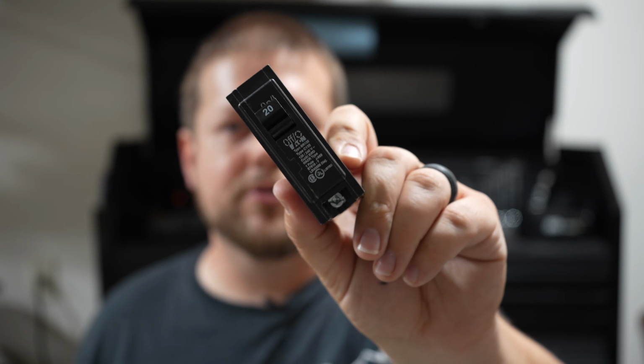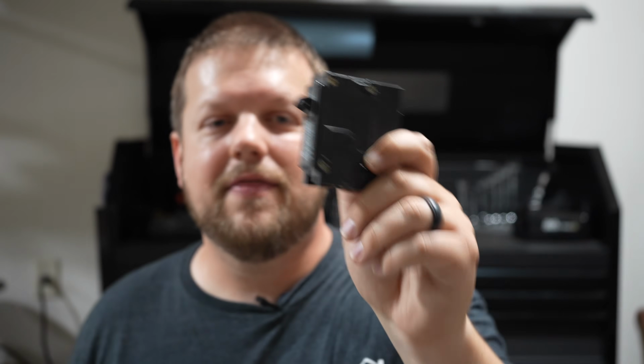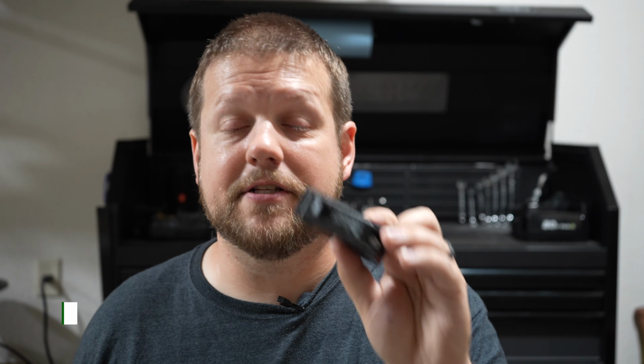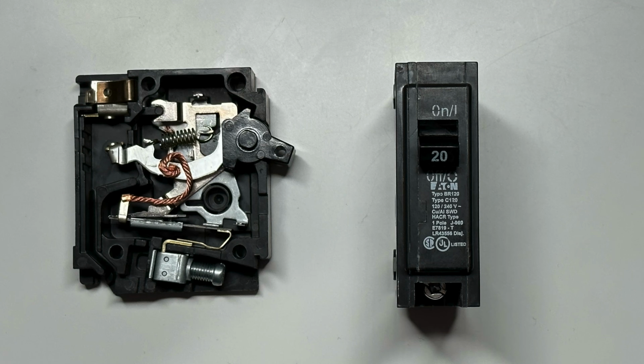Believe it or not, circuit breakers are not designed to last forever, and they can go bad over time. So if you're having problems with the electrical system in your house, how do you know what the problem is and if it's actually the breaker that's causing the issue? Well, one of the main signs of a bad breaker is that you start to see some physical damage to it. So it could be an indication that it's been getting too hot over time and the plastic is starting to break down. You might start to see cracks in the cover and in the casing. This is a good indication that the breaker itself is bad and needs to be replaced.